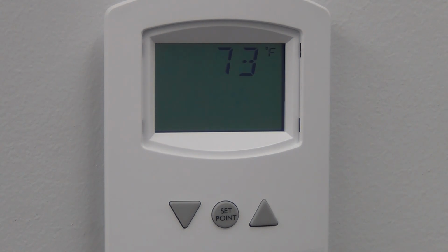Setting up a Simply VAV controller starts by pressing and holding the up and down arrow buttons at the same time. In controllers without passwords, the display changes to the configuration screen after a few seconds. If a password is required, you would have to enter it before the configuration screen is shown. From the configuration screen, you can press up or down to choose other functions such as communication or balancing. These topics are covered in other videos.